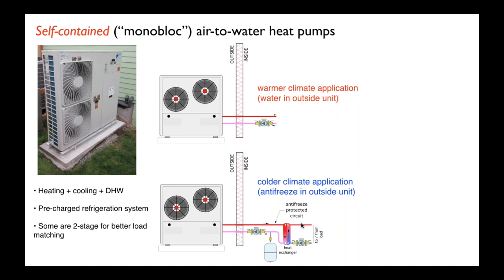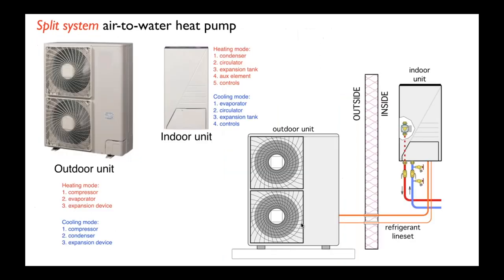So that works. It might be appropriate where you've got a system with a lot of volume in it and you really don't want to use perhaps a 30% solution of propylene glycol throughout the entire system. It might be an older system where you just want to keep the water side of it isolated from antifreeze. So those are two fundamental ways you can pipe up a monobloc.